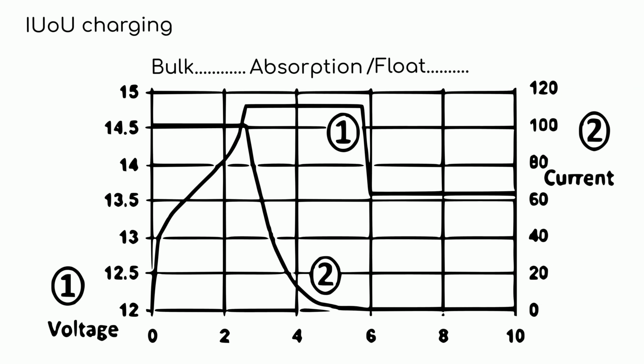This mode, in the case of lead-acid batteries, is self-discharge compensation due to the chemistry. And in the case of LFP cells, it is simply a voltage set below the resting voltage.